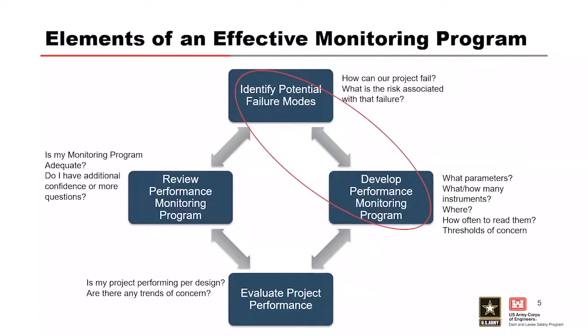Another element is developing the performance monitoring program: what parameters are we monitoring, how many instruments do we need, where should they be located, how often should we read them, and what are our thresholds of concern? Once we establish a baseline, do we set a window — for example, if a piezometer reading goes above a certain level for a given reservoir elevation — that triggers some sort of action?